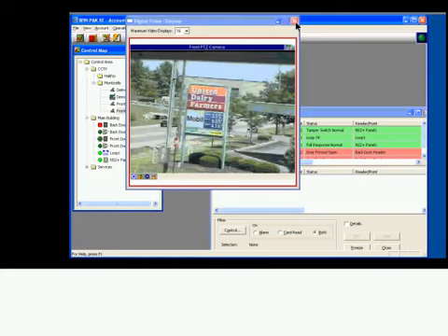You can. The Rapid Eye Multimedia LT, the whole Rapid Eye line, was geared towards dial-up. So as far as efficiency goes with that, you've got it. The main concern is the speed over your phone lines with the Winpak integration. Can it work? It definitely can. I have a customer using a leased line modem that is actually doing this. But the intention originally was you dial up the site, you retrieve the data, and you hang up. So it really wasn't geared for live monitoring, so there's not a lot of bandwidth. No, we don't want to do live monitoring on it.